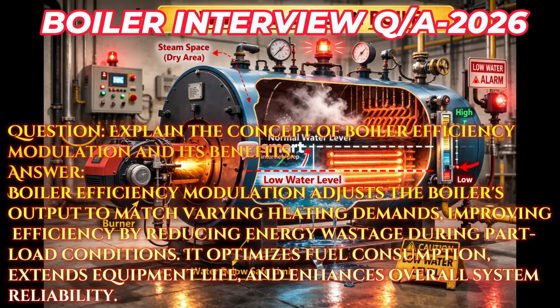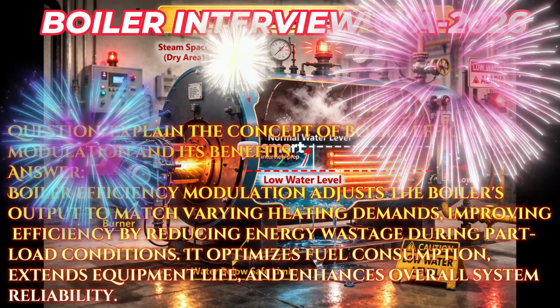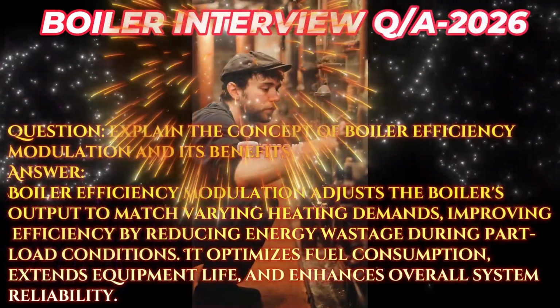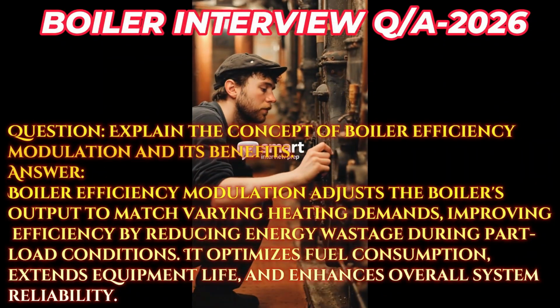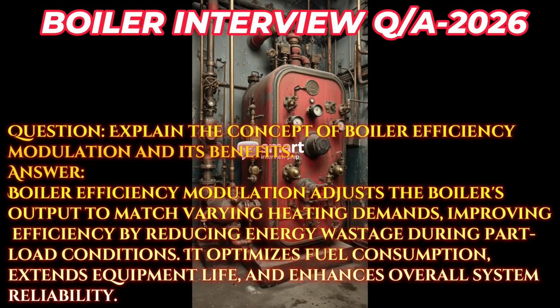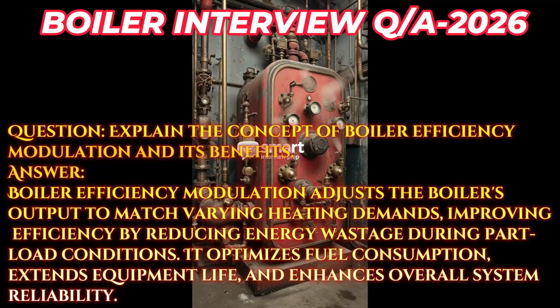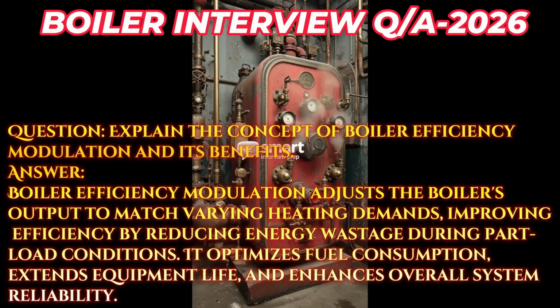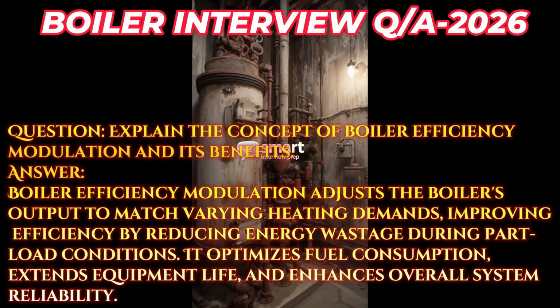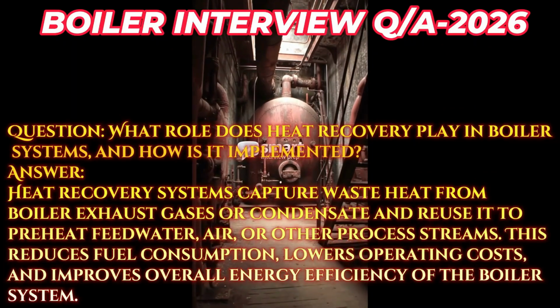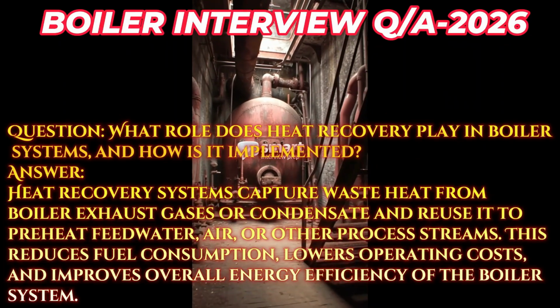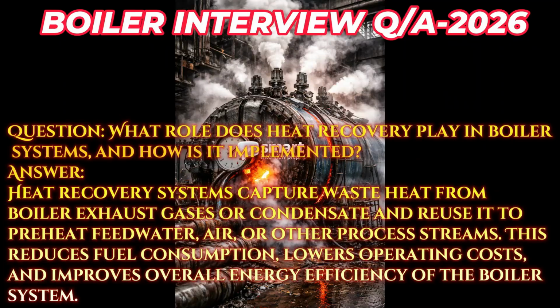Answer: boiler efficiency modulation adjusts the boiler's output to match varying heating demands, improving efficiency by reducing energy wastage during part load conditions. It optimizes fuel consumption, extends equipment life, and enhances overall system reliability. Question: what role does heat recovery play in boiler systems, and how is it implemented?